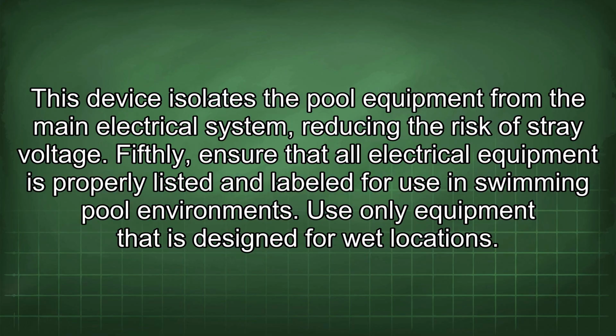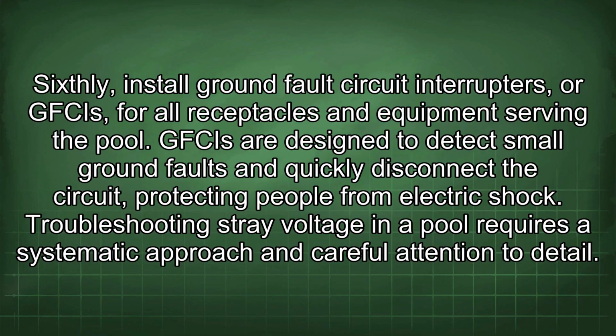Fifthly, ensure that all electrical equipment is properly listed and labeled for use in swimming pool environments. Use only equipment that is designed for wet locations. Sixthly, install ground fault circuit interrupters, or GFCIs, for all receptacles and equipment serving the pool. GFCIs are designed to detect small ground faults and quickly disconnect the circuit, protecting people from electric shock.